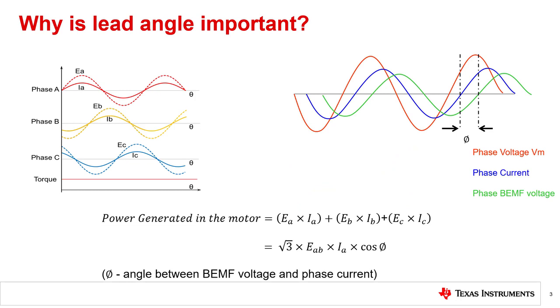In this slide we are going to see why lead angle is an important parameter in BLDC motors. The instantaneous power generated in a BLDC motor is the sum of the product of back EMF and current in each phase of the motor. The average power generated depends on phi, which is the angular phase difference between the phase back EMF voltage and phase current.